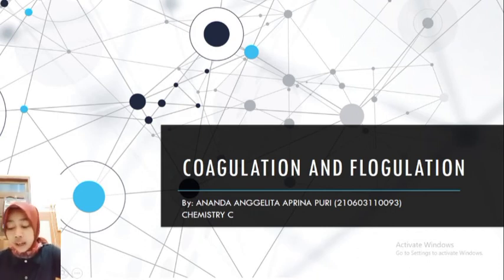For example, colder water usually slows coagulation and flocculation reactions, which may require more time to achieve optimal floc formation. Extreme pH values, high or low, will also interfere with the process. Coagulant effectiveness is highly dependent on pH. For some coagulants, alkalinity is a factor.